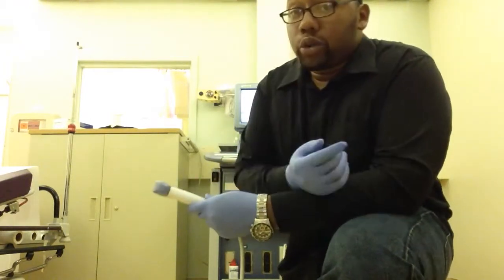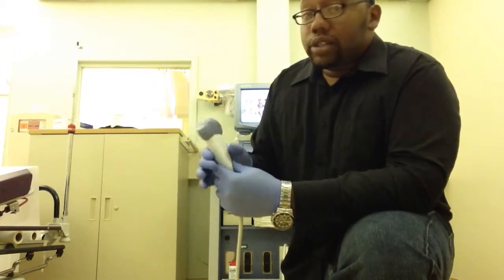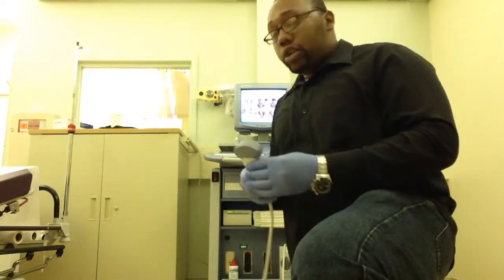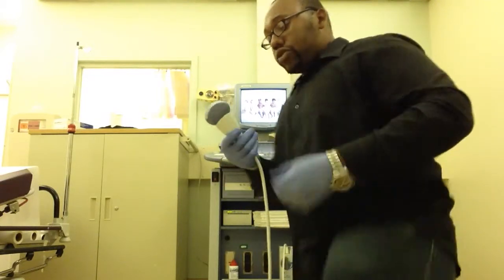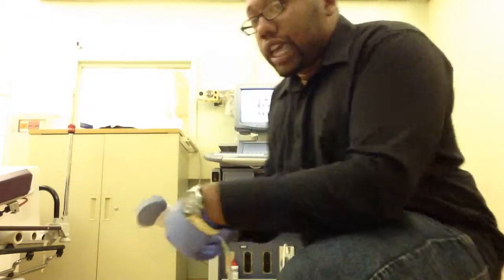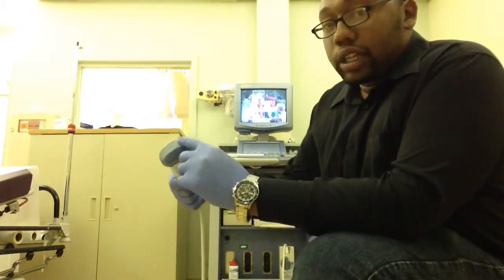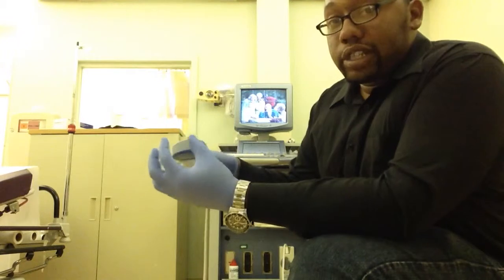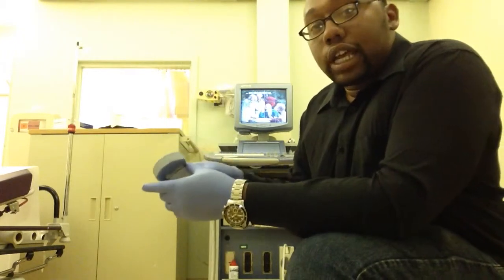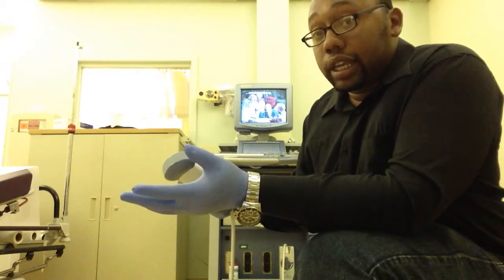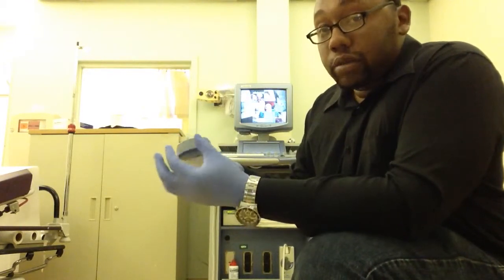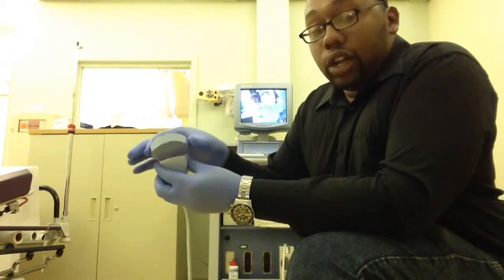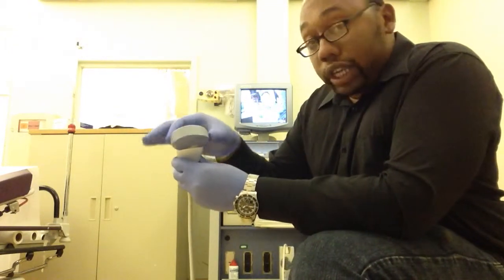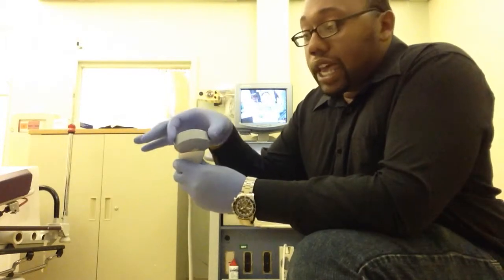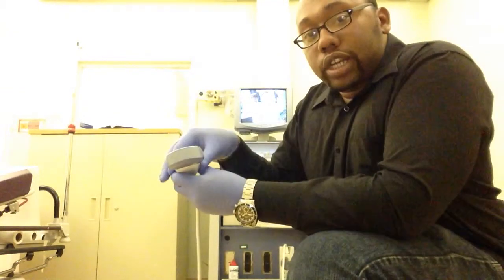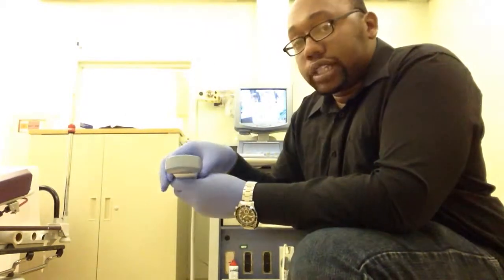Now, we're going to look at troubleshooting. What if these transducers are not working right? There's a couple of things that could be happening. Okay? In terms of troubleshooting, as a biomedical engineer, you want to look at a few things. You want to make sure that there's no swelling around this front lens, because this is where the sound is emitted from. It basically works like a collimator, the same as we see in X-ray and in CT. It focuses the beam of sound. Everything on the side is made with an acoustic absorbing material on the inside, so there's no sound escaping outside of that window that the ultrasound technician is trying to examine.